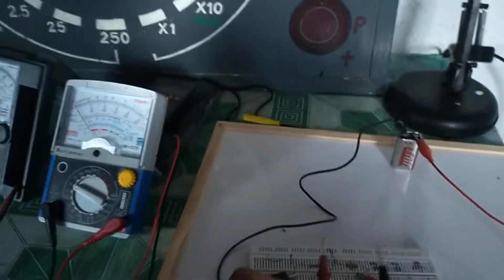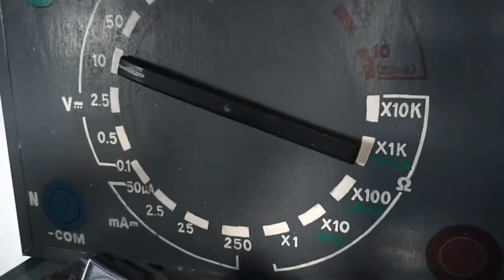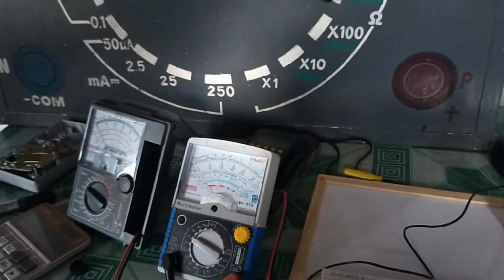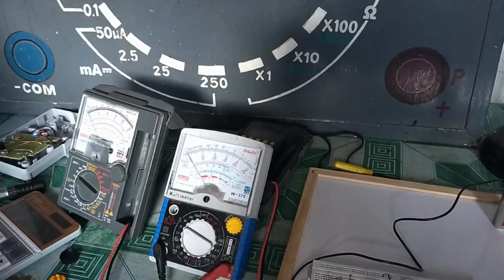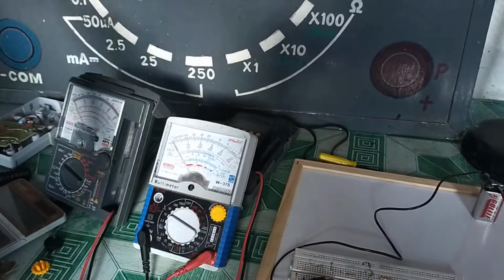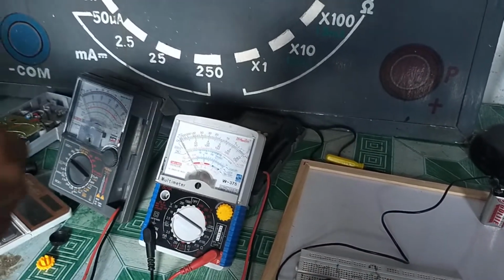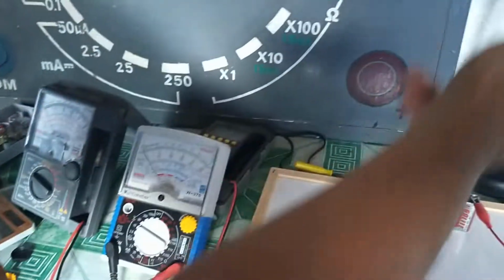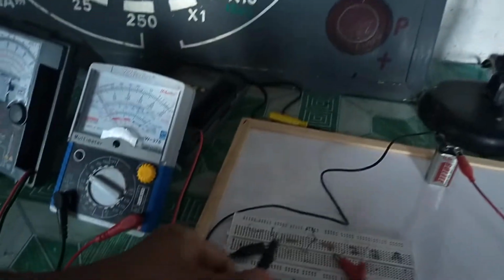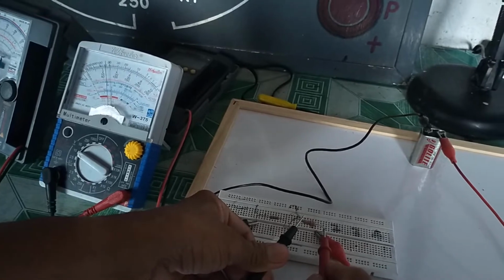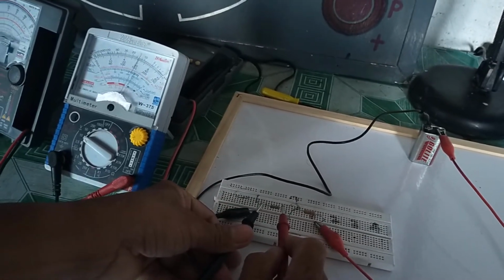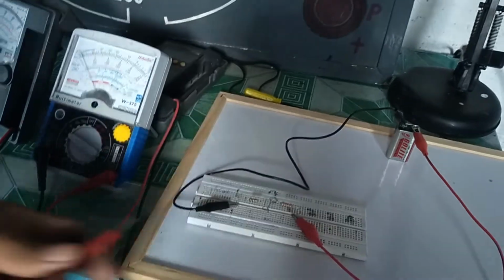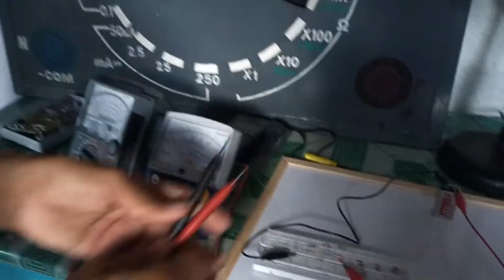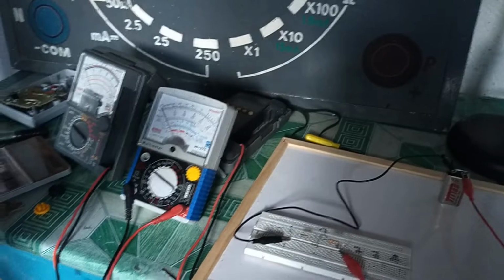Because if it is inverted in polarity, the pointer moves in the opposite direction, just like this. Oh, look at that one now. The negative test rod of your voltmeter is connected to the positive side. That is inverted polarity. The pointer moves in the opposite direction. So meaning to say, that indicates that your polarity is not correct with the power supply. So it should be like this. Okay? Just like that. Okay. That's the way you connect your test rods when measuring voltages, just across the component that you are going to test. No?